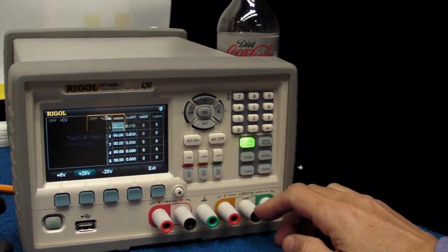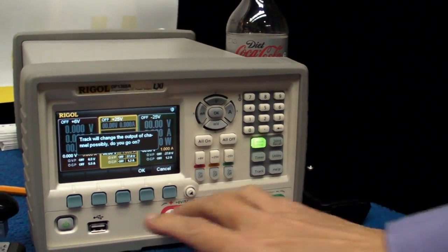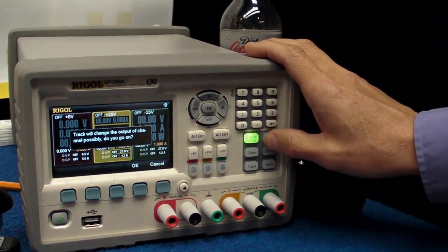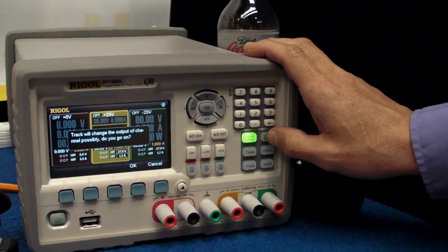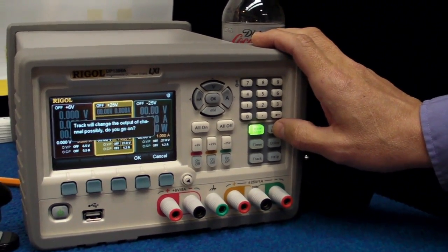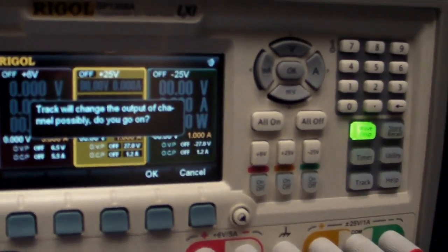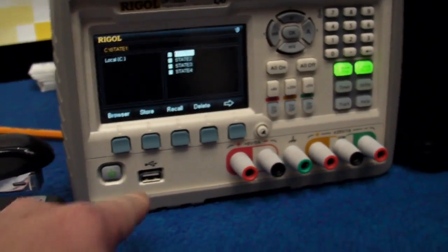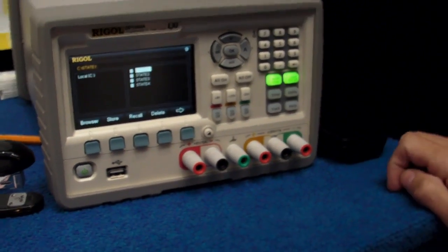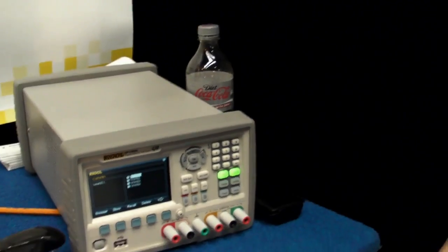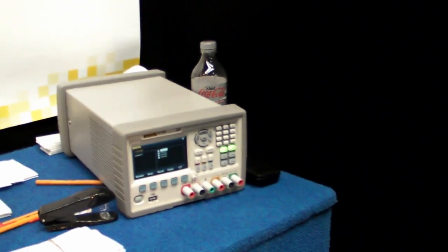Fantastic. Okay, they can operate in a dual tracking mode. Yep, on the multi-channel from front panel positioning, but primarily they're just a programmable power supply via the interfaces. Fantastic. Looks very nice. And what's the USB host for? Yep, USB host is for basically you can have settings that are on the USB host that can be pulled into the unit to operate the unit. Oh, okay, so you can just walk along with the key, plug it in, and then update the output. Yep, that's right.